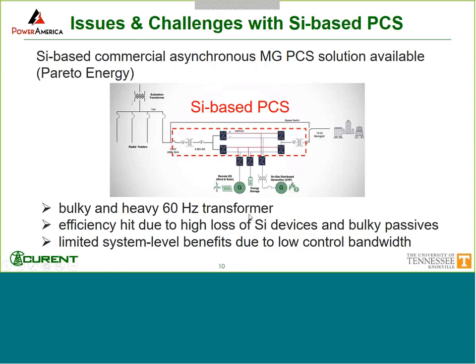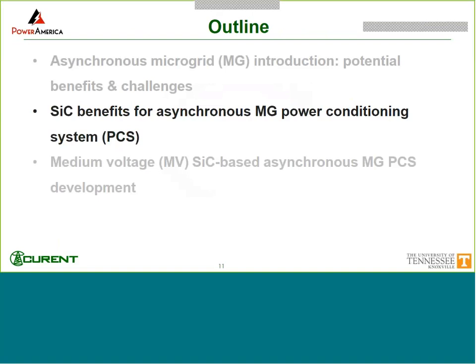Also, because these IGBTs are relatively slow, at 3.3 kV you have to use fairly high voltage IGBTs, and they can only switch around a kilohertz or less. So some of the system level benefits I mentioned are limited because of the limited control bandwidth. So with that, we said, okay, why don't we use silicon carbide for this? We first analyzed the potential benefits of silicon carbide for the asynchronous microgrid PCS. In particular, we like to use relatively high voltage silicon carbide, namely a few kV.